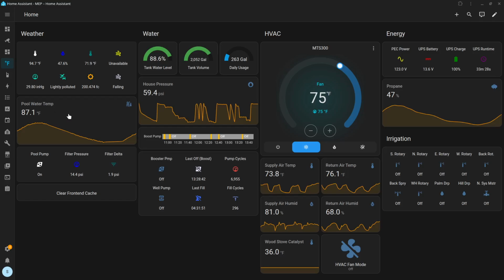Jumping down here, we have pool water temperature. This is, again, a Dallas sensor within a stainless steel probe well that is in one of the ports of a three-way T on the return line of my pool pump. With some thermal goo in there as well for good heat transfer, but it's directly in the stream of water. This updates only when the pool pump here is running, which is controlled and scheduled through Home Assistant here. That ESP controller actually has a contactor that it pulls in to start or stop that pump, which also provides the status. This temperature updates only 30 seconds after the pump has started, and then every 2 minutes after that.